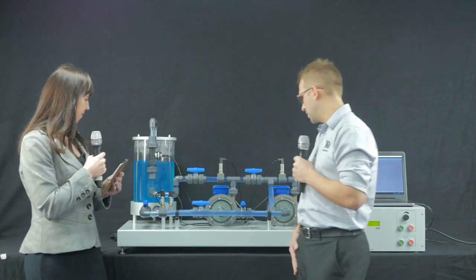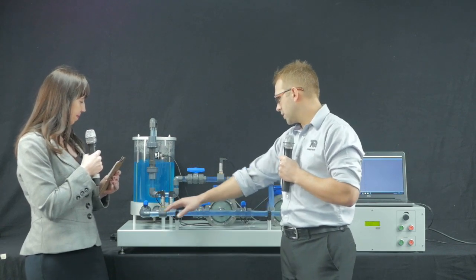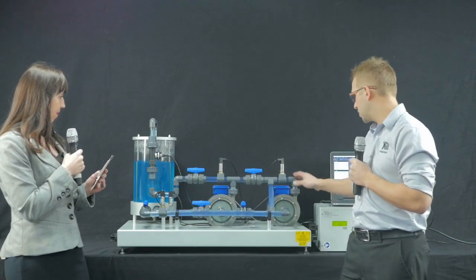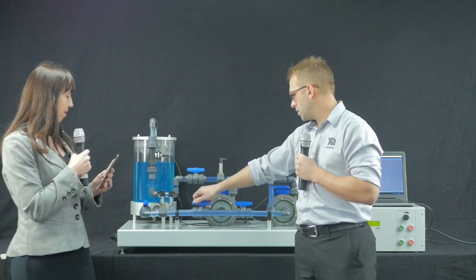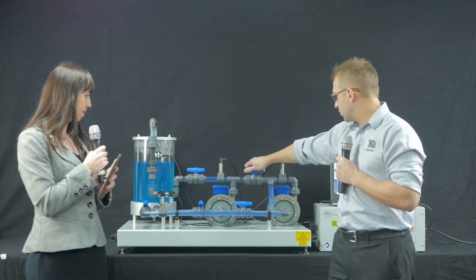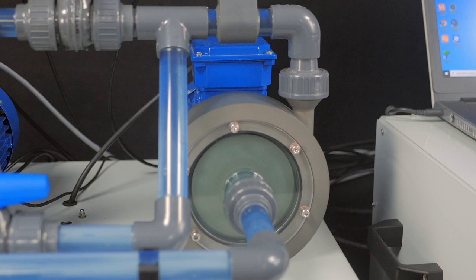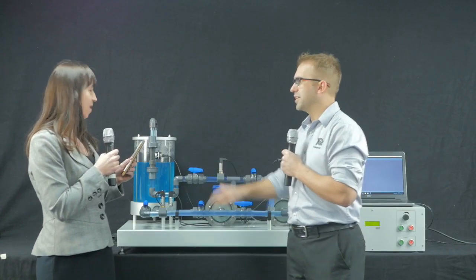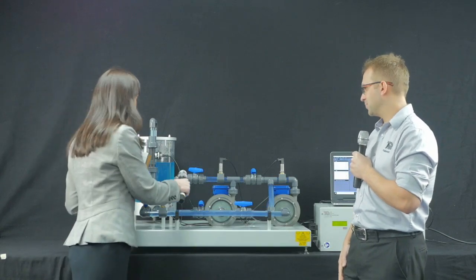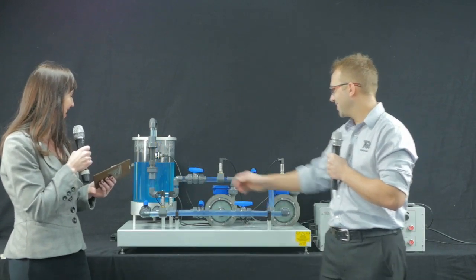There we go. We're up to speed. Let's put it in the other formation, shall we? So, we'll leave it running, and we will set it up in series. From pump number two, we want to feed into pump number one. We'll close this port here so that pump number one can't suck from the tank, and force the water to go down there. Now we're running in series. And you mentioned we could throttle it using this valve. There you go. You can hear the pumps. We're making them work a little bit harder there.